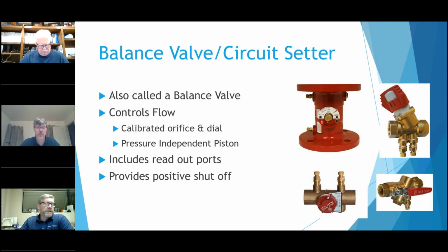Some of the things that you might have on the outlet of the pump are balance valves. Basically, it just adds pressure drop to the system or to the pump. You're able to turn this dial down just to add pressure to the pump to move it around on the curve. I'll touch a little bit later on what that looks like as far as the curve, to make sure you get the right flow out of the pump.